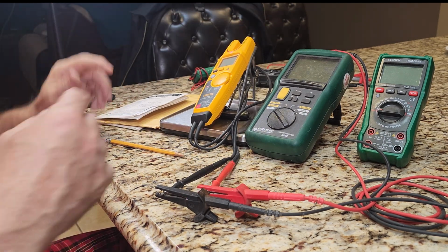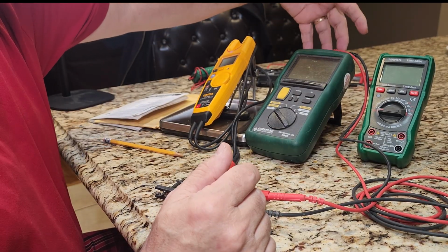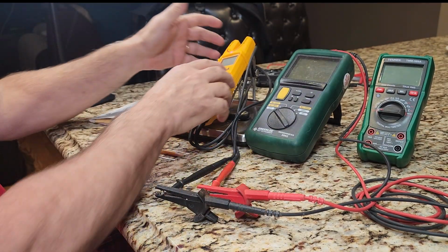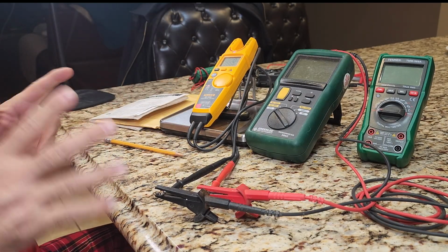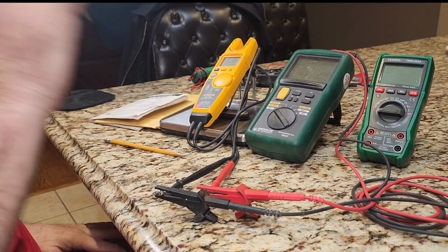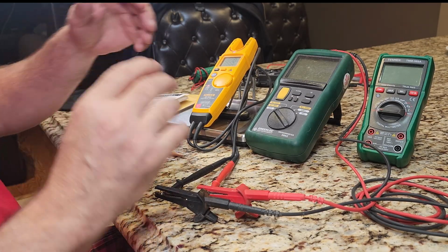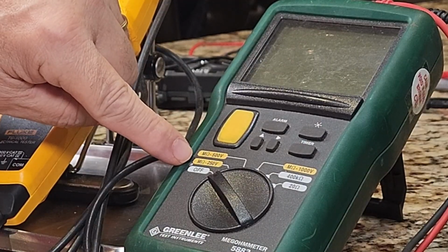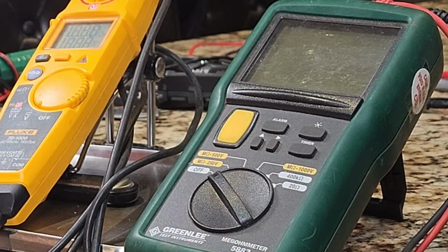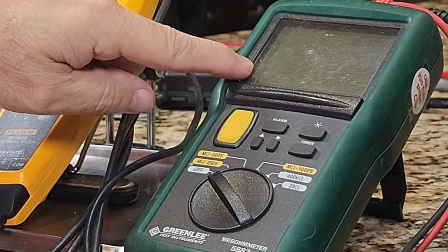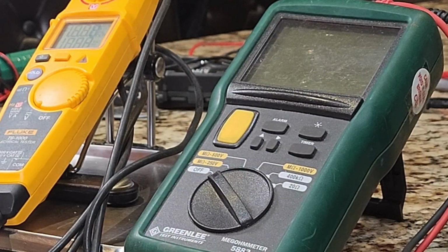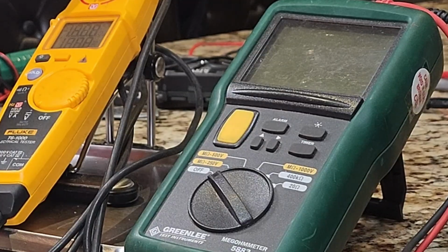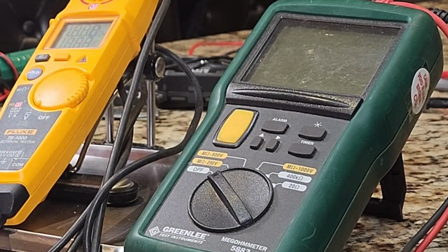All right. So what I've done was I've taken the alligator leads and I put them into the megohmmeter, taking them out from that one. So first thing we're going to do is we'll turn on this meter, right? Now, I will say that a megohmmeter has usually 5 position settings. It has 3 powered settings. If you look on here, they're yellow. They're yellow for a reason because they're caution. They actually induce a super high voltage. This meter with the 6 AA batteries can put out up to 1,000 volts. That's insane. Right. So we should read 1,000 volts on this meter, DC, but at a microcurrent.